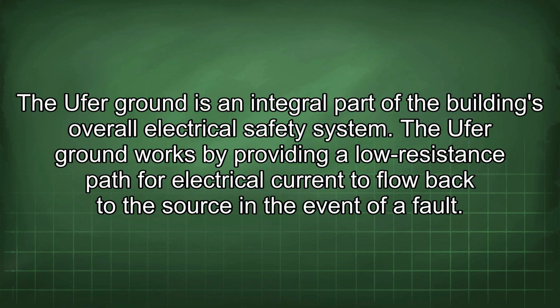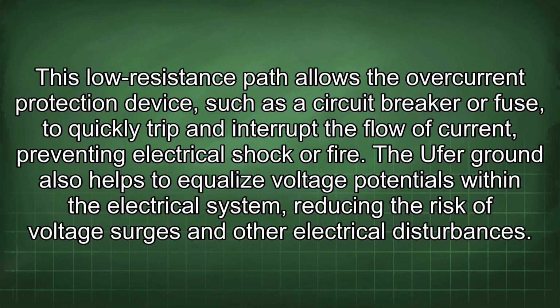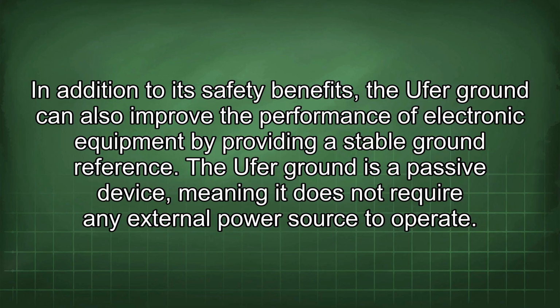The Ufer ground works by providing a low-resistance path for electrical current to flow back to the source in the event of a fault. This low-resistance path allows the overcurrent protection device, such as the circuit breaker or fuse, to quickly trip and interrupt the flow of current, preventing electrical shock or fire. The Ufer ground also helps to equalize voltage potentials within the electrical system, reducing the risk of voltage surges and other electrical disturbances. In addition to its safety benefits, the Ufer ground can also improve the performance of electronic equipment by providing a stable ground reference.